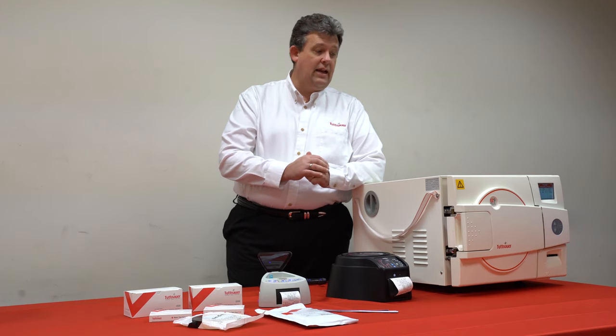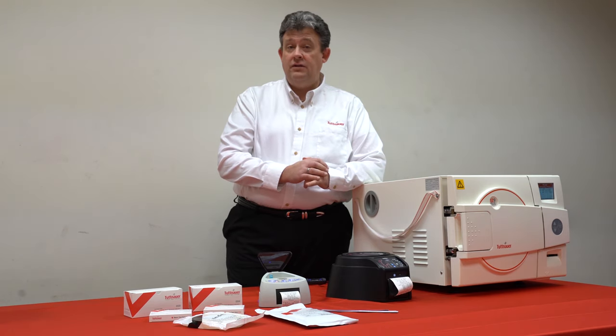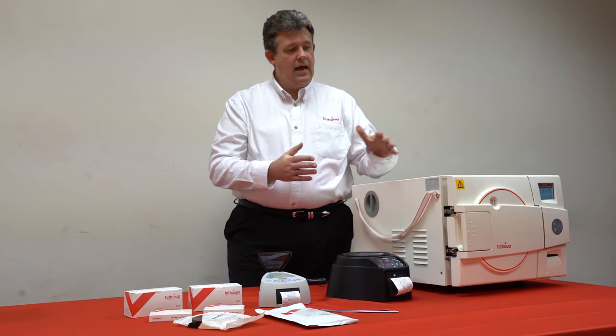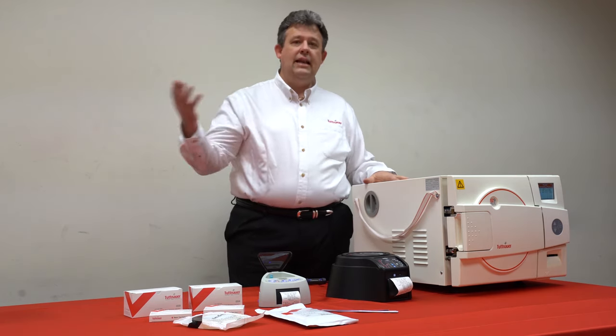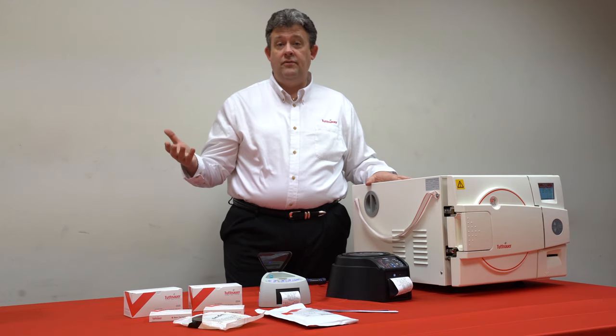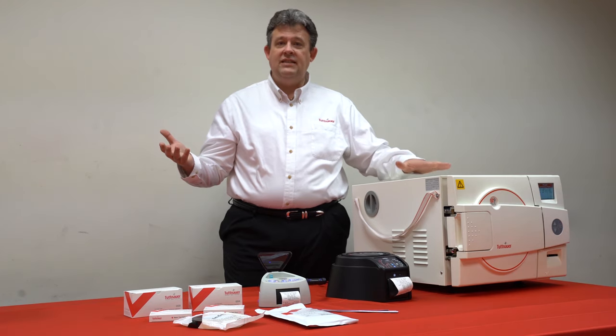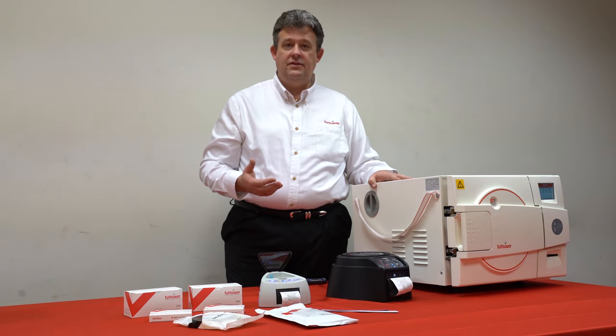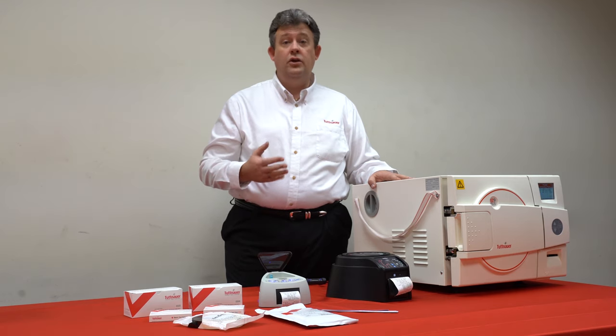The biggest glaring weakness I see — and this is in the dental market — is that they have a mail-in program. That mail-in program is insufficient as far as the guidelines go, and it doesn't really make sense. How do I test for bacteria on one day, send it out, wait five or six days for the results, and then if I get a positive result for bacteria, I've now spent six days sterilizing instruments and have to go back and notify the patients? It compromises patient care and puts the practice at a huge risk.